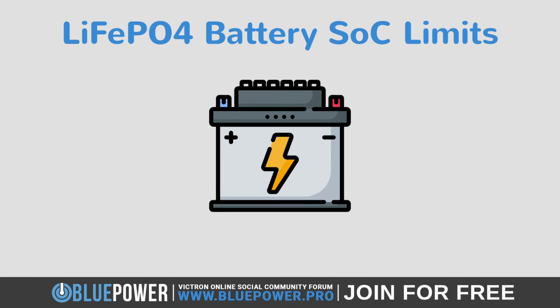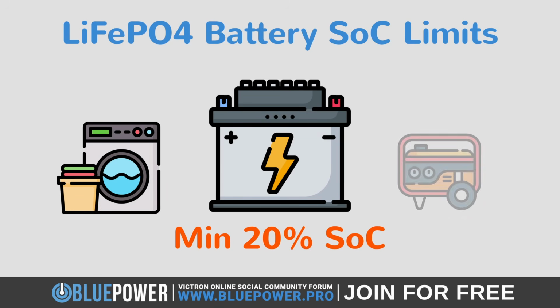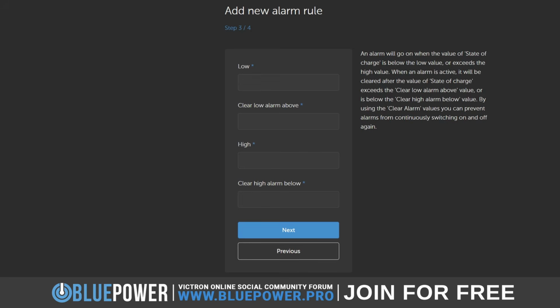The low value will be when the battery gets to a dangerously low state of charge percentage, or close to it. This will depend on your needs and preferences, but do note that the lowest safe state of charge of lithium phosphate batteries is 20%, making that a good value to enter here. Although you probably want to be warned before it reaches this point in order to lower your loads or manually start a generator. In that case, you could set it to something like 30 to 40% instead.